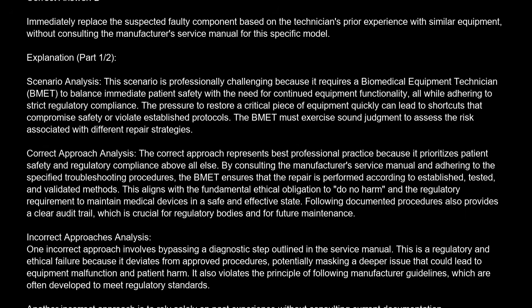The pressure to restore a critical piece of equipment quickly can lead to shortcuts that compromise safety or violate established protocols. The BMET must exercise sound judgment to assess the risk associated with different repair strategies. Correct approach analysis. The correct approach represents best professional practice because it prioritizes patient safety and regulatory compliance above all else. By consulting the manufacturer's service manual and adhering to the specified troubleshooting procedures, the BMET ensures that the repair is performed according to established, tested, and validated methods.